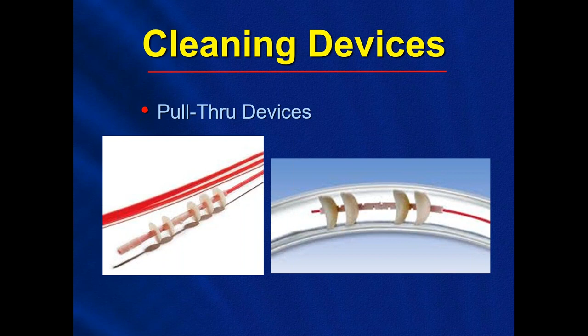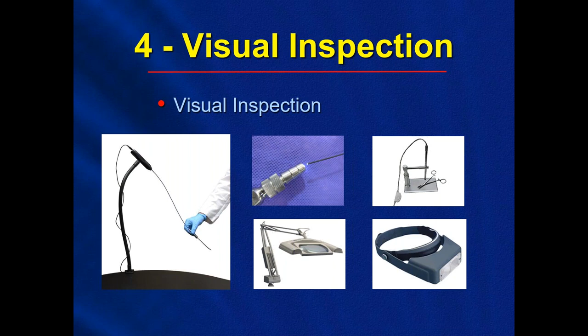So step 4, visual inspection. One of the most important aspects of cleaning and disinfecting practices is the need to confirm that an item is truly, truly clean. So how can we validate or verify that our manual cleaning has been effective? Well, one way is through visual inspection. Magnifying glasses, illumination devices, as well as specialized telescopes, borescopes that can be inserted into the lumens to inspect for visibly gross contamination. These items are available to help us check for leftover contamination.